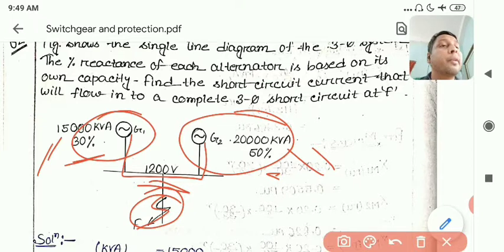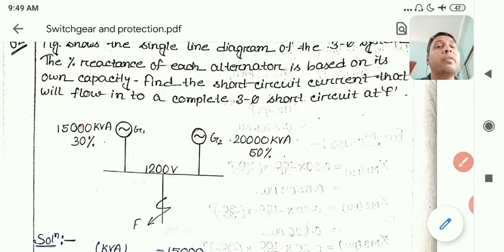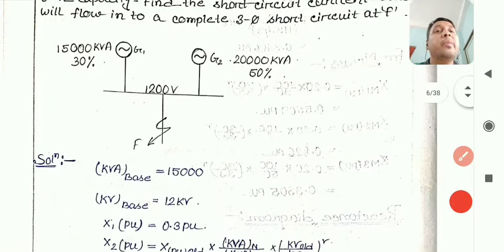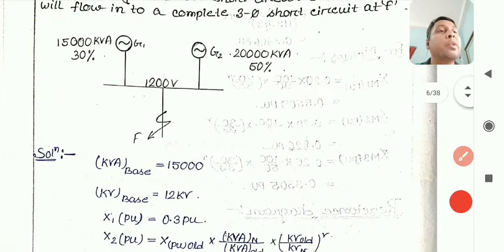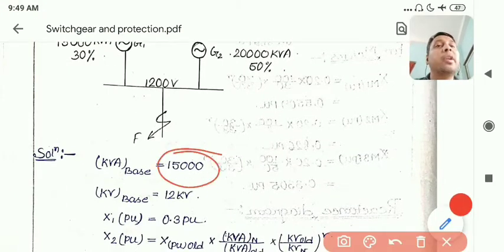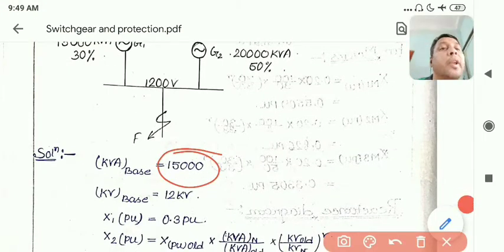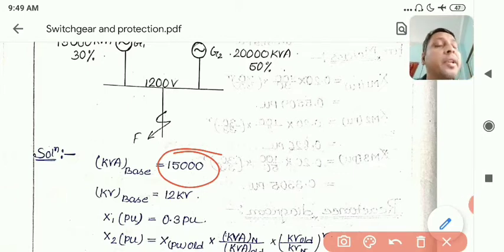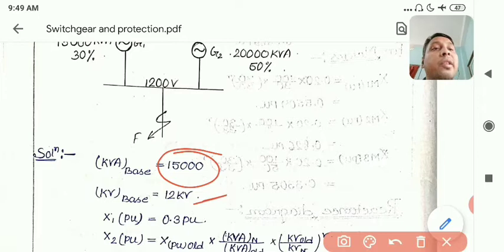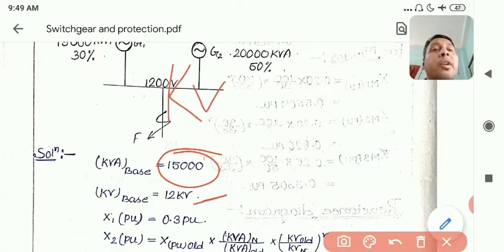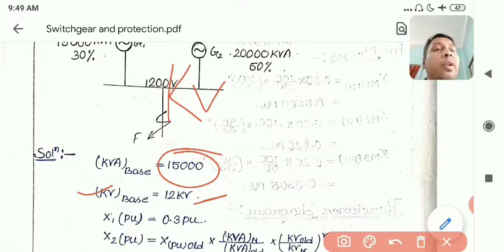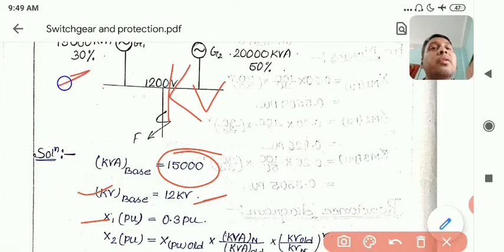Since no base KVA is specified, we can assume any base. We have chosen 15,000 KVA as the base KVA. The base voltage is 1200 KV (or 12 KV — to be noted). For Generator 1, since it is already on its own base, the per unit reactance remains 0.3.